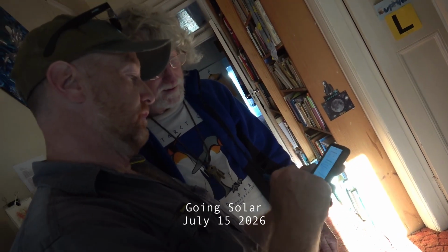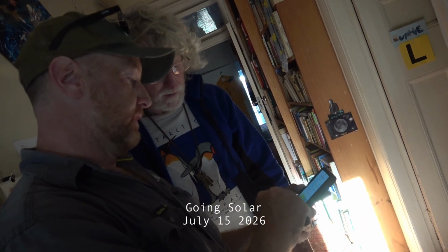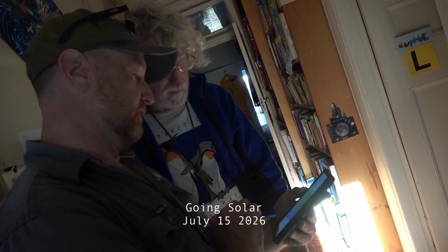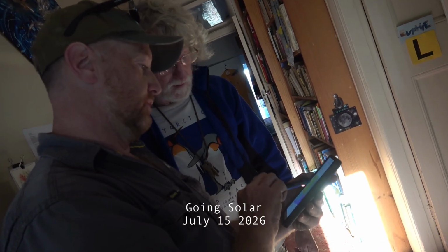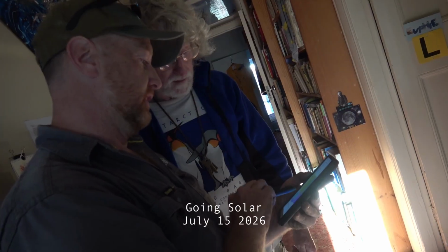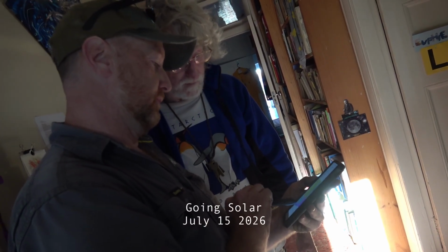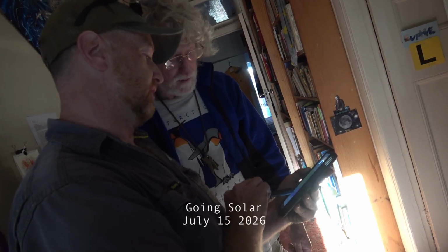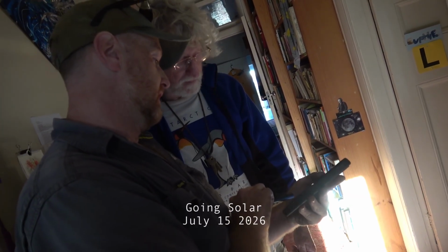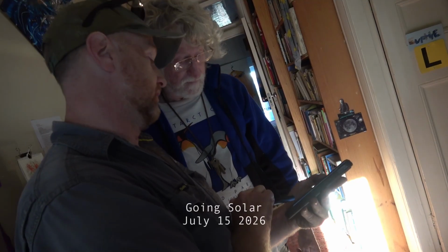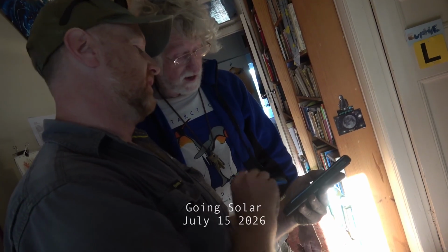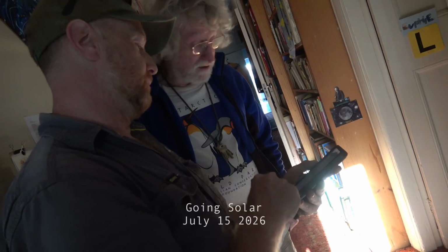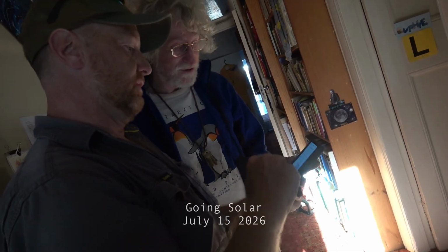But I could just show you maybe this person here. You can see that they've produced 15 kilowatts today. 13 of those kilowatts went to the battery. The remainder went to the load, and of the 5 kilowatts that she's used on her load, 3.2 came from the battery and the rest came from solar. And she's basically taken nothing from the grid. You're always going to get a little bit down here. No matter what you do, it's always going to happen.